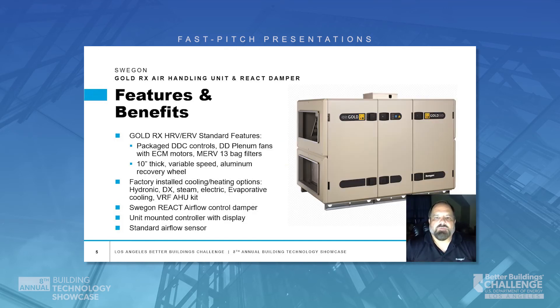The features and benefits of the Swegon Gold Heat Recovery Unit include packaged DDC controls, direct drive plenum fans with ECM motors for variable airflow control, MERV 13 bag filters, and a 10-inch thick aluminum heat recovery wheel with variable speed control. As an option, modules can be added to the unit for heating and cooling, including hydronic coils, DX coils, steam, electric, evaporative cooling, etc.